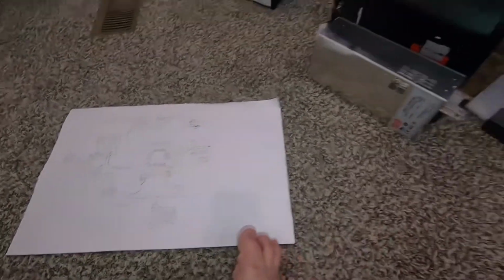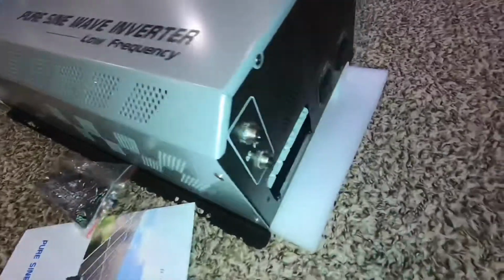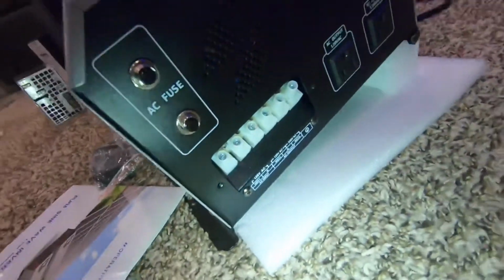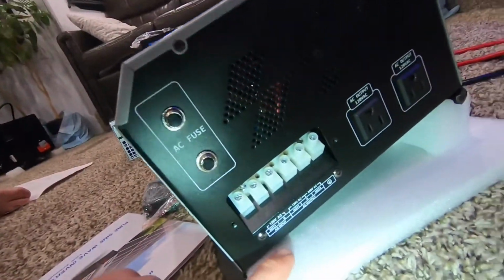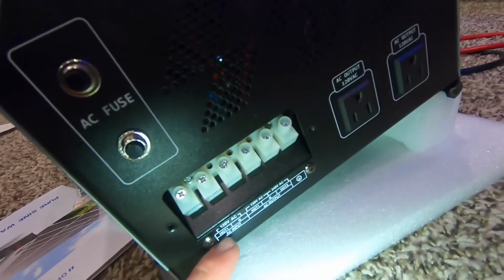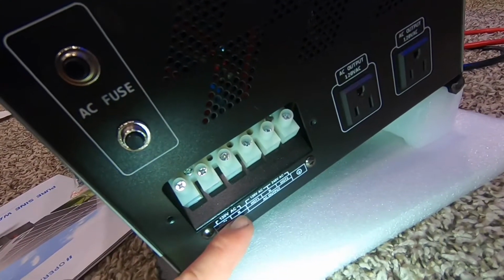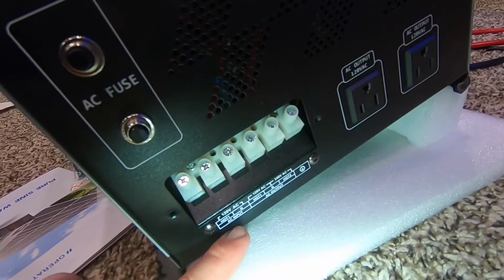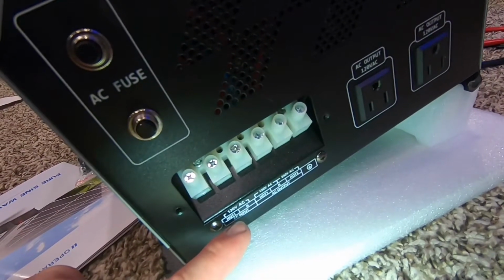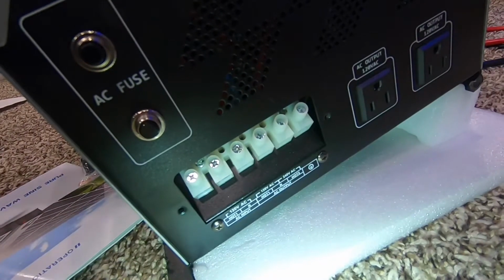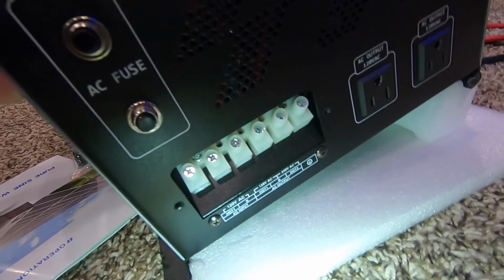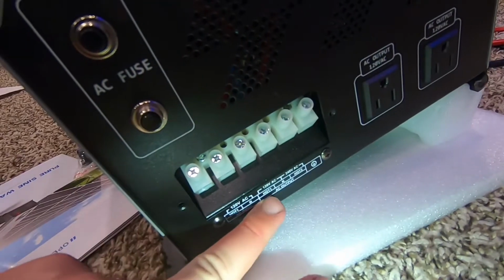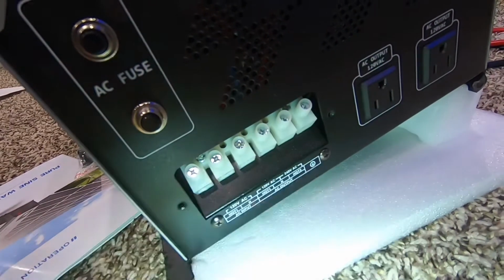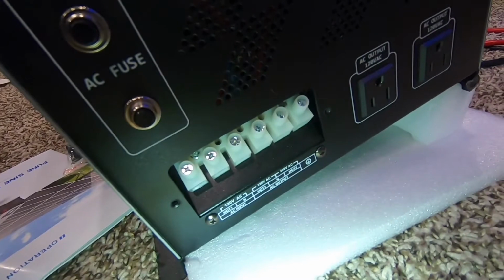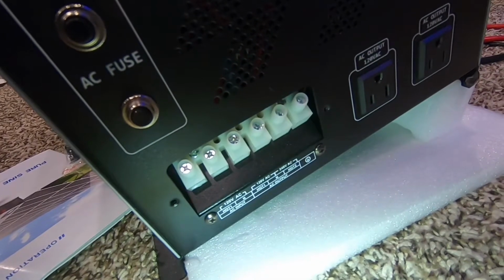That way the AC input function, coming back over here on the inverter itself, this is your AC input. It's only a hot and a neutral, 120 volts. If you can turn that on and off, that's the AC input the inverter senses to start charging. The others are your hot 1, hot 2, neutral, and ground, your 4 typical wires going to your AC panel from shore power.